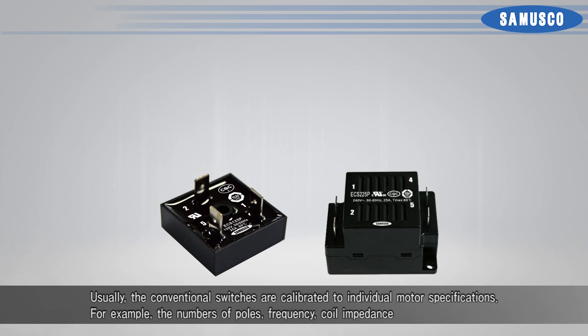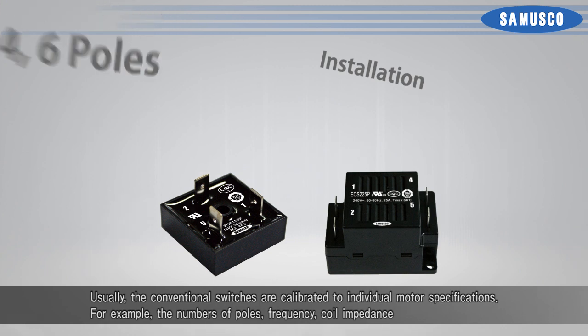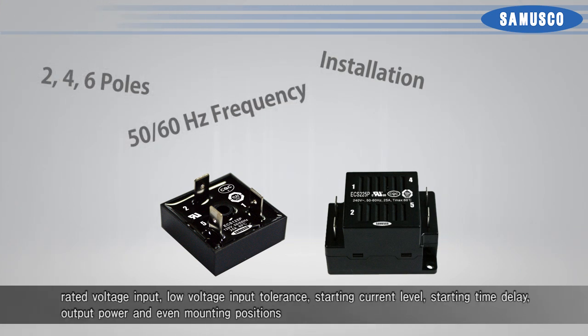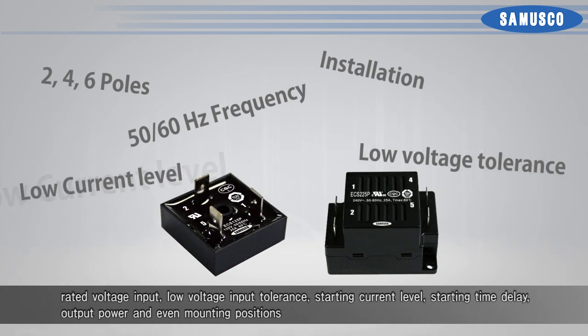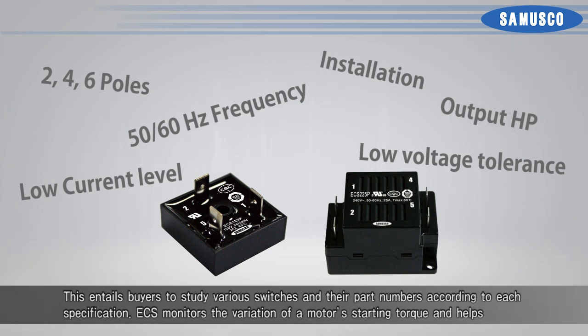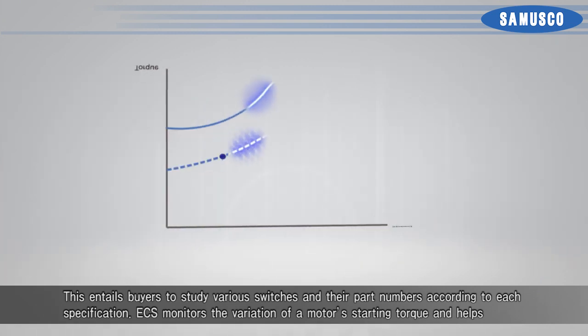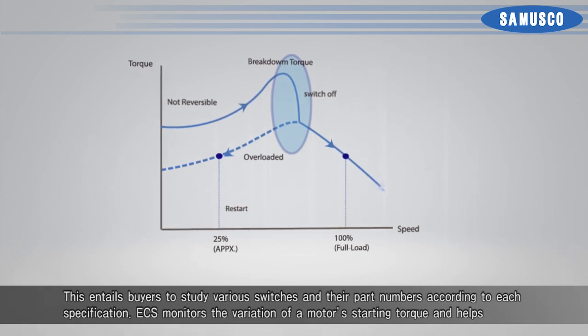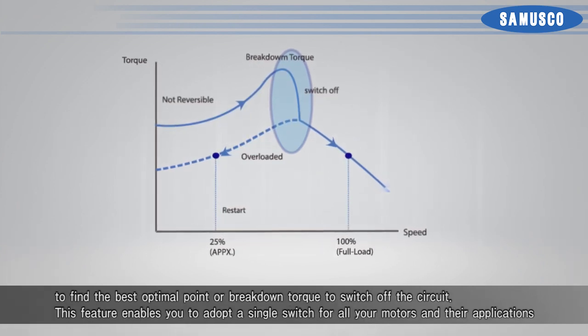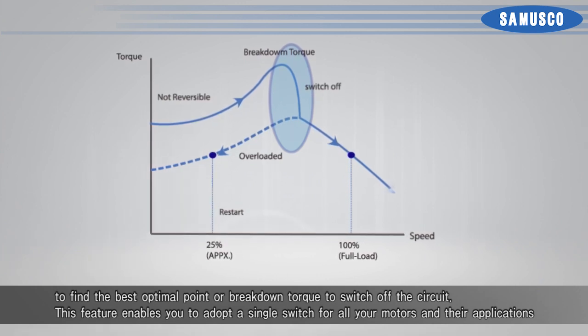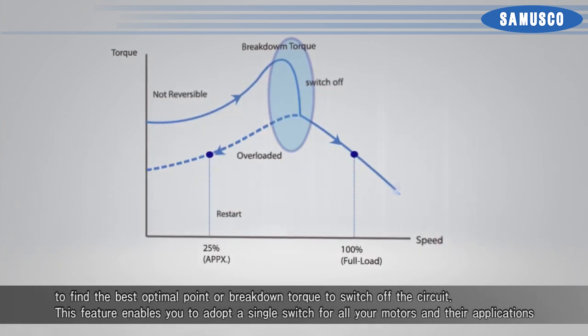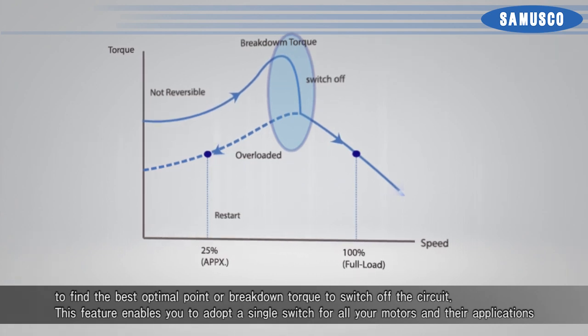Usually, the conventional switches are calibrated to individual motor specifications — for example, the number of poles, frequency, coil impedance, rated voltage input, low voltage input tolerance, starting current level, starting time delay, output power, and even mounting positions. This entails buyers to study various switches and their part numbers according to each specification. ECS monitors the variation of a motor's starting torque and helps to find the best optimal breakdown torque to switch off the circuit. This feature enables you to adopt a single switch for all your single-phase motors and their applications.